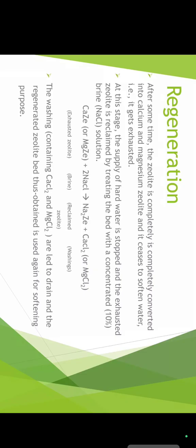The calcium zeolite reacts with sodium chloride to form sodium zeolite and calcium chloride. Likewise, magnesium zeolite reacts with sodium chloride to form sodium zeolite and magnesium chloride. So the exhausted zeolites are calcium zeolite and magnesium zeolite, and the washings are calcium chloride and magnesium chloride.